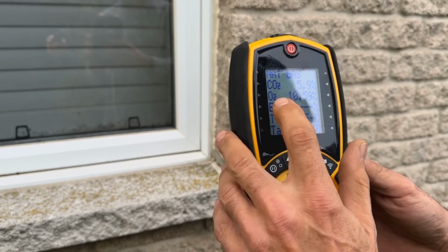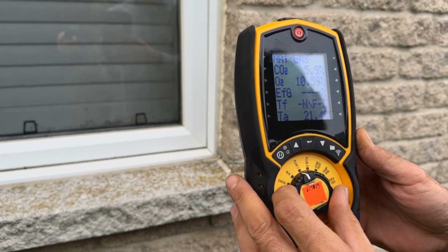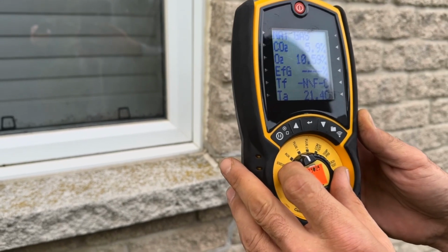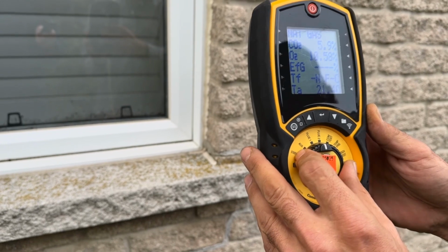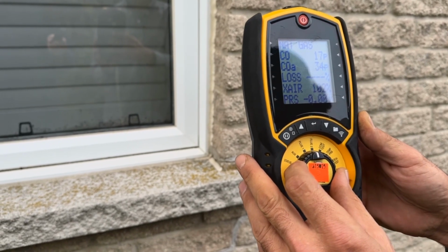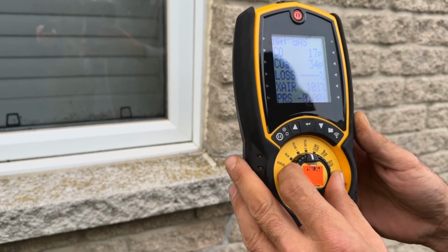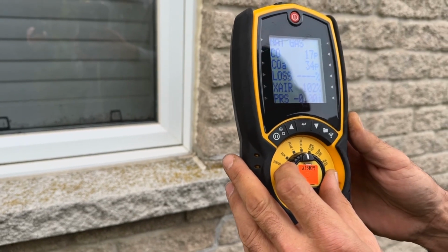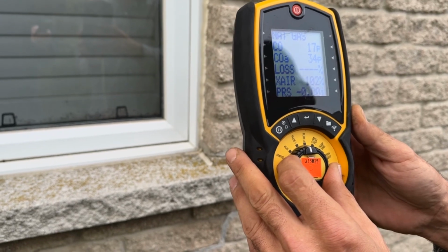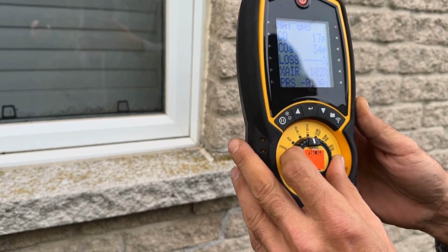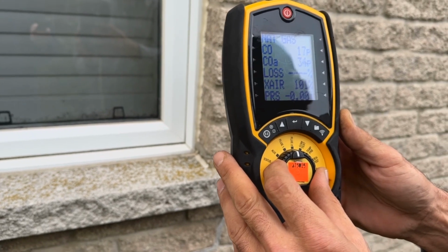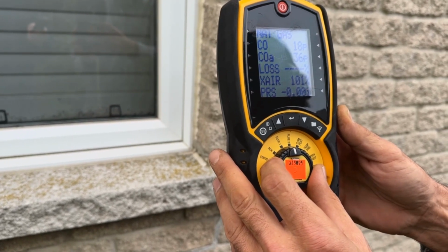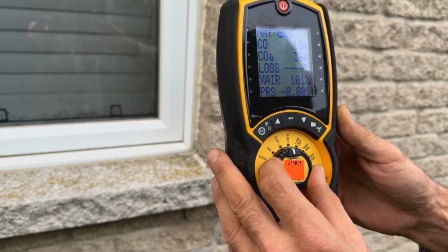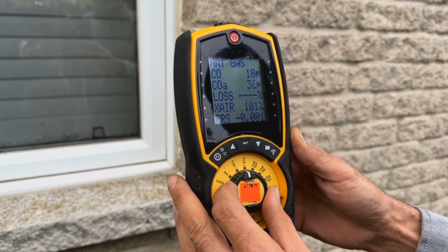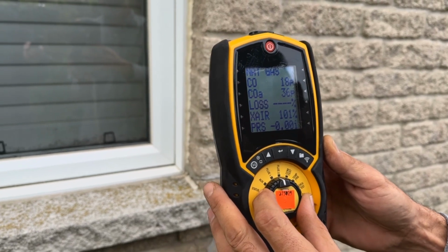I also go to this part here, and that's going to give me the CO2 percentage, 5.9. Most of my meters, I'm seeing that reading maybe bottom out at 9.5. So CO 17 parts per million, which is good. Not bad. Just so everybody knows, the furnace has been running for a good 15 minutes now. The way you do it is crank your thermostat temperature up and let it run, that way the furnace settles out. I've already flushed and primed my trap, so I'm not going to get any CO there. Burners are clean, gas pressure is good, and we're at 18 parts per million, so my furnace survives one more winter.